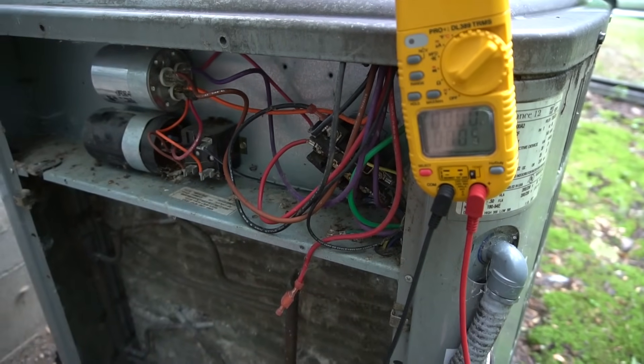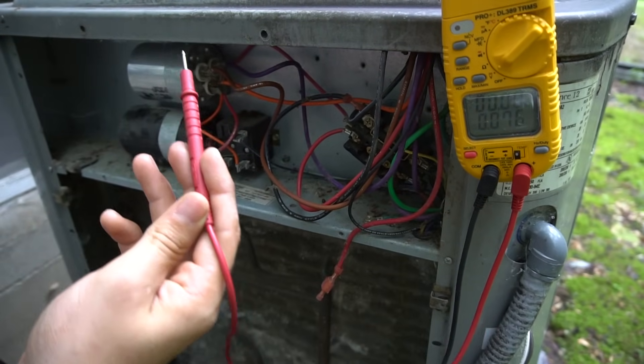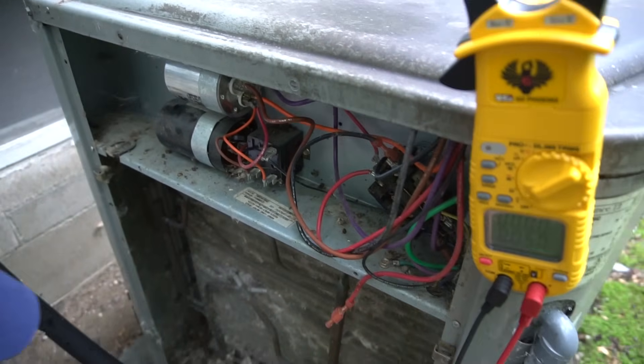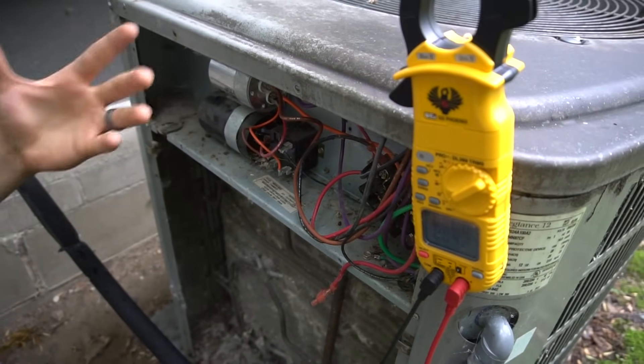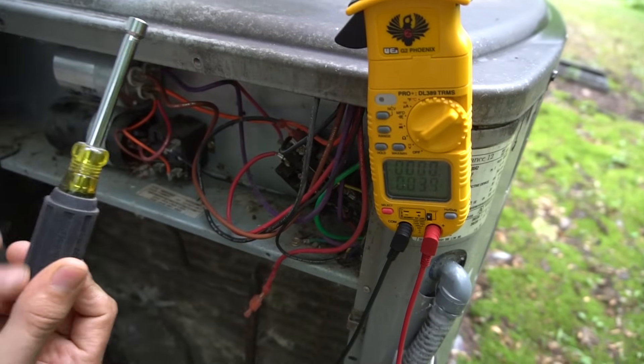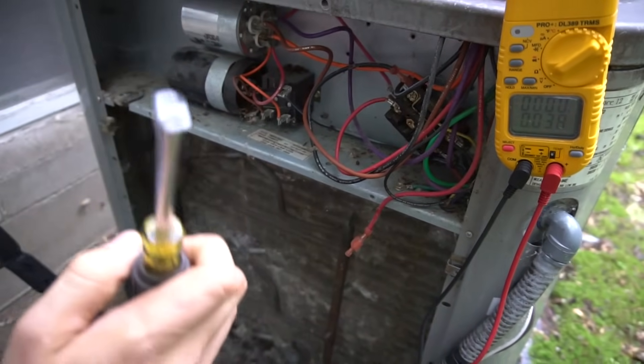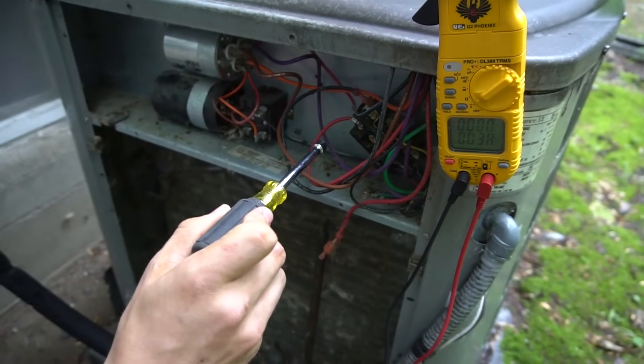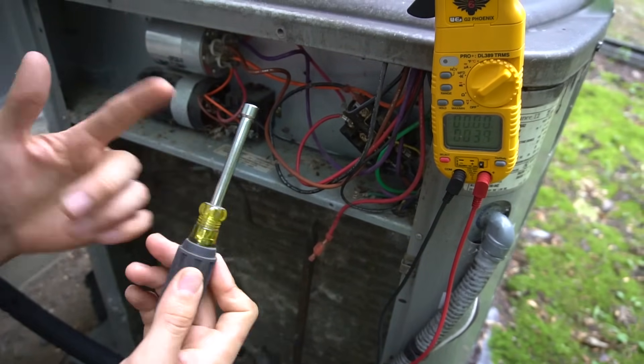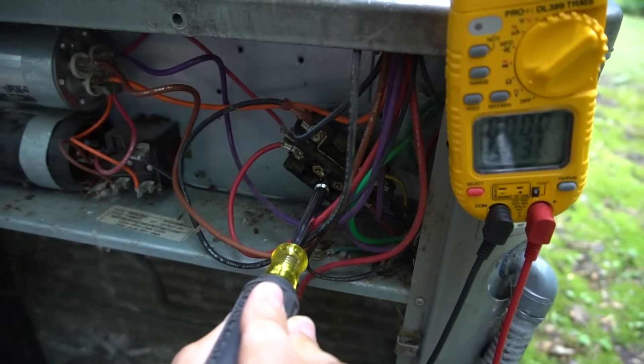Once the thermostat is calling for cooling, this little plunger will pull in, let the voltage through, and both my fan and compressor will turn on if everything is working. For example, if you use an insulated screwdriver, you can press that little plunger in. Be wary of this because it is 240 volts — if you touch something metal you can get shocked and it'll probably melt your screwdriver. So very carefully press the little plunger in and see what happens.